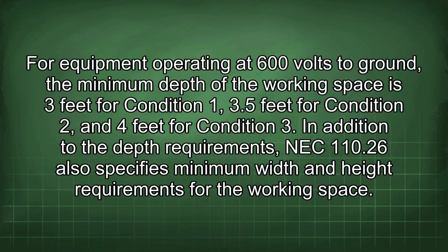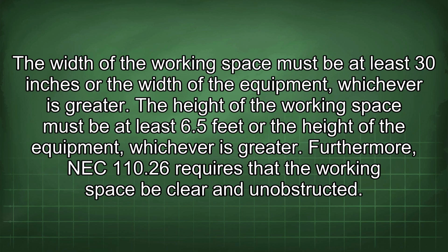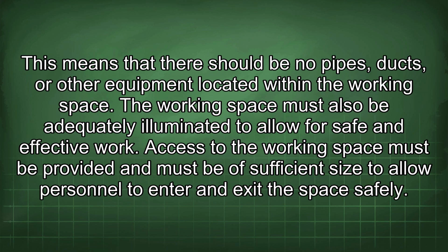In addition to the depth requirements, NEC 110.26 also specifies minimum width and height requirements for the working space. The width of the working space must be at least 30 inches or the width of the equipment, whichever is greater. The height of the working space must be at least 6.5 feet or the height of the equipment, whichever is greater. Furthermore, NEC 110.26 requires that the working space be clear and unobstructed. This means that there should be no pipes, ducts, or other equipment located within the working space.